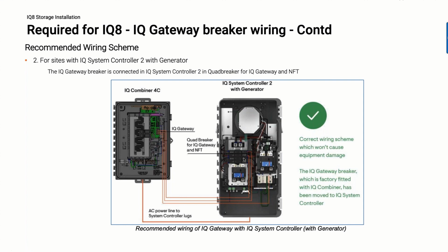There is a third method to power the IQ gateway from the system controller common bus, which isn't shown here. And that's to wire the Envoy directly to the backup loads panel. Since the backup loads panel is connected to the system controller bus, this method is an approved one. Installers, any of these three methods will work to move the power from the combiner bus to the system controller bus. The important thing is you have to move it with IQ8 microinverters, and that's the best practice.